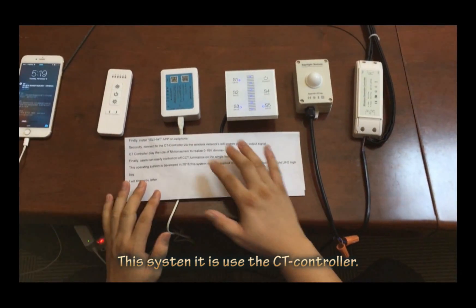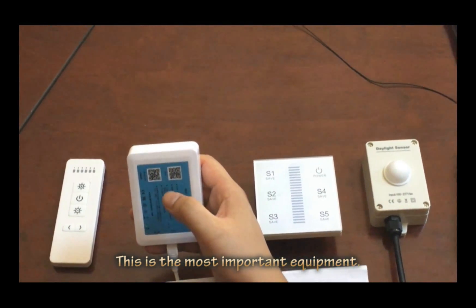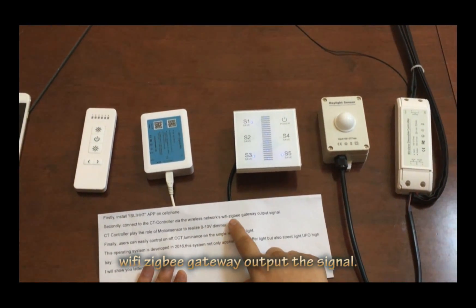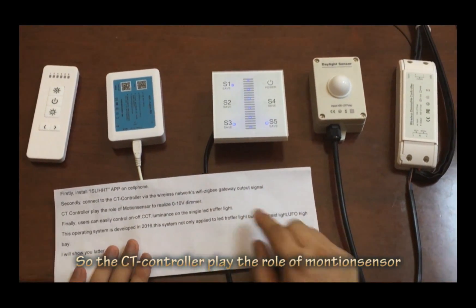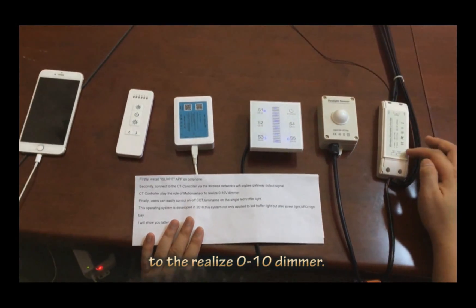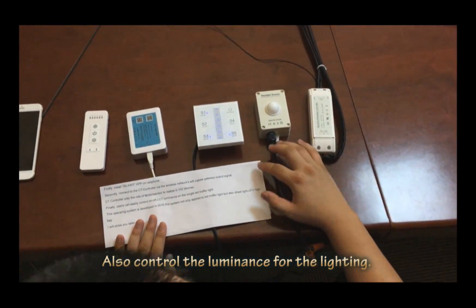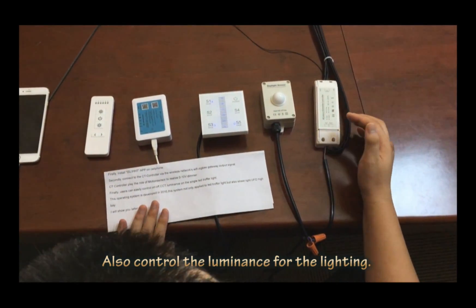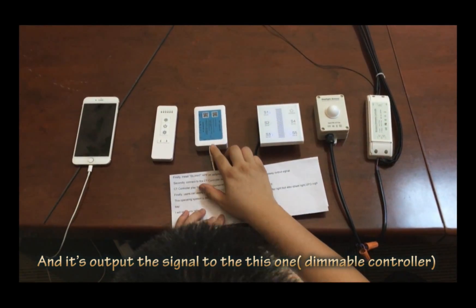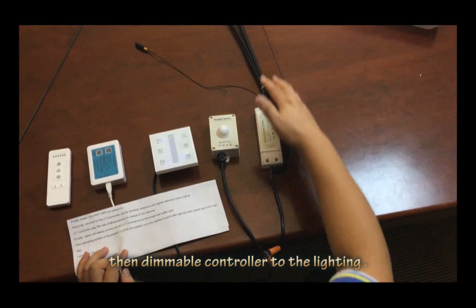This system's key function is the CT controller — this is the most important component. The CT controller receives the wireless network — Wi-Fi, ZigBee — and gateways output the signal. The CT controller plays the role of relaying from the motion sensor to the zero-to-ten-volt dimmer, so the user can easily control the light on and off, control color temperature, and output the luminance signal to the lighting. The CT controller outputs the signal to the dimmable controller, and then the dimmable controller goes to the lighting.